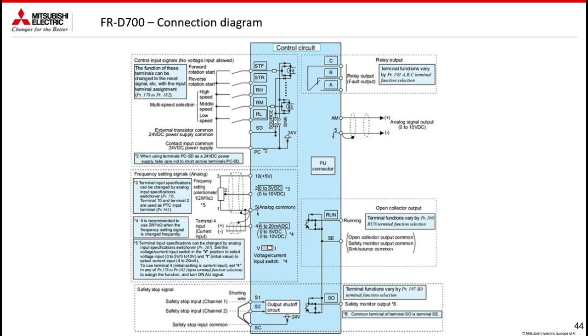potentiometer wiring. Still talking about inputs, we see the safety SC is a 24 volt positive, and by default it will be supplied bypassed as a double jumper, which will end up on S1 and S2. And the 0 volt is always the common SD. SD is the common reference for everything digital, while the pin 5 is the common reference for everything analog.